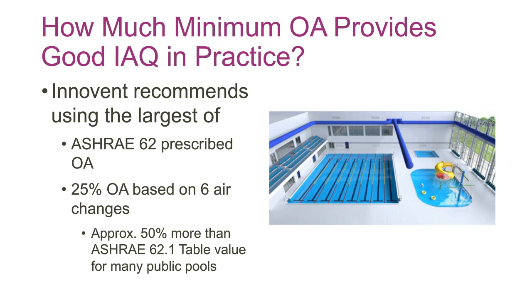And the reason we recommend that is because we found it works. It works very well. It works with various air distribution, and that's one of the key things. I mentioned up front that water treatment is important and air distribution is important, but a system that is using fresh air provides a lot more flexibility and covers up a few sins so that you may not have to be absolutely perfect on those other things for your system to work. And so, it's a more real world type of system in my view.